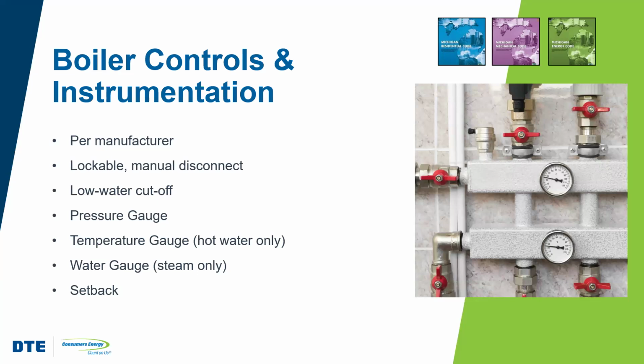We're also going to have some controls and instrumentation on these boilers, right? We're going to have low water cutouts, right? This is another safety device, right? This automatically shuts off the boiler if the water level drops below the operating level, right? So that the boiler doesn't dry fire, right? You're going to have a pressure gauge, right? This is going to indicate the pressure inside the boiler. It's going to help the operator, in this case the homeowner, be able to monitor what that operating pressure is and make sure that it is at a safe and efficient level.